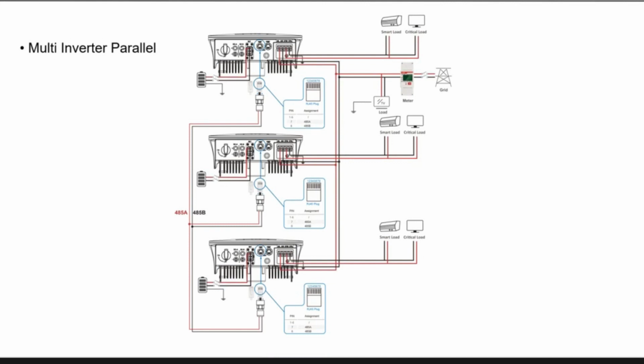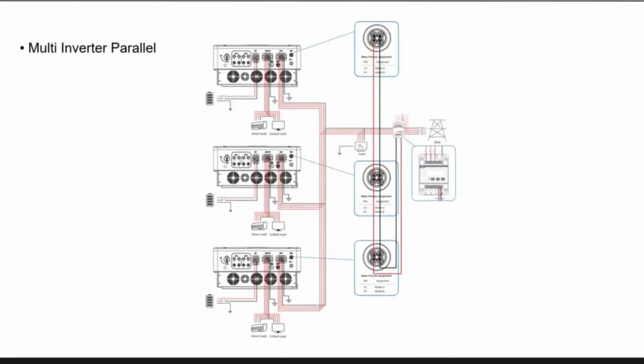This shows you that's a single phase hybrid. We'll jump there. That shows you parallel connections, multiple connections for single phase inverters. And this is what we were talking about earlier for the three-phase inverters, where this connects into COM1 at the top on the input on the bottom of the inverter. Out of there, you'd have one that'd be the master, and then connected down, in and out to the next one, and then in and out to the next one, and then back to the meter. So that one would actually be set as the master, because that's the first one that comes back from the meter, and then these other two would be slaves that take their information from the master inverter, and so on and so forth.